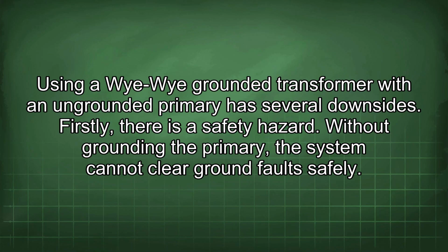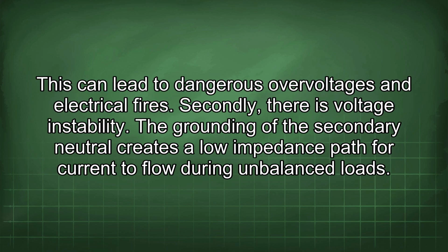Using a Wye-Wye grounded transformer with an ungrounded primary has several downsides. Firstly, there is a safety hazard. Without grounding the primary, the system cannot clear ground faults safely. This can lead to dangerous overvoltages and electrical fires.